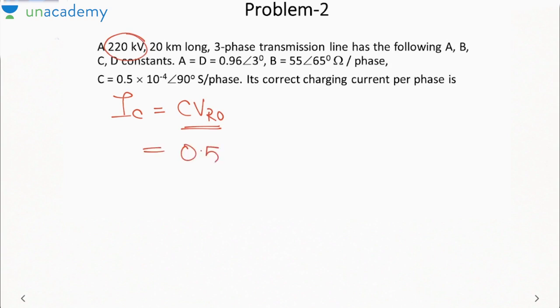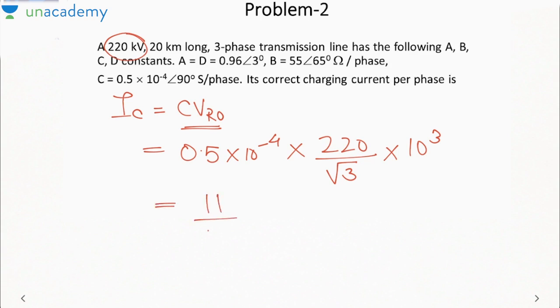So C is 0.5 into 10 raised to power minus 4. Since charging current is calculated per phase, it will be 220 by root 3 into 10 raised to power 3. Remember, a transmission line is always considered to be in star connection, so we have to take VL by root 3. So it will be 11 by root 3 ampere. This will be your line charging current per phase.